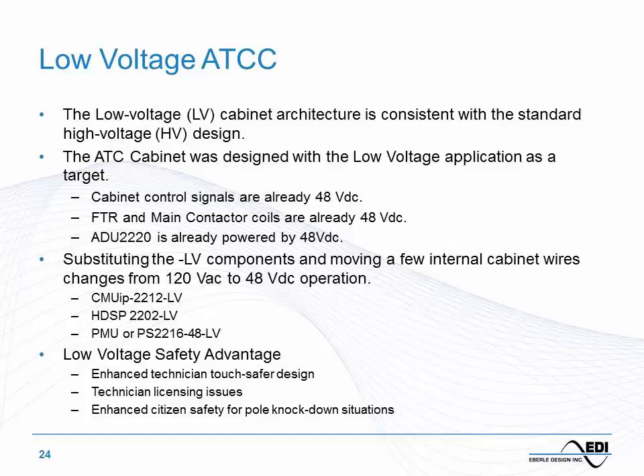Different agencies will have different motivations for deploying low-voltage cabinets — technician safety, licensing issues, citizen safety, and others. Cabinet inventories can remain the same; new cabinets procured as 48-volt will be identical to 120-volt cabinets other than components and power connections. Several LED manufacturers are already providing 48-volt DC compatible signal heads — red, yellow, green, arrows, peds, countdowns — all configurations needed to outfit an intersection. Low-voltage ATC cabinets are a look to the future, with several deployments around North America right now.